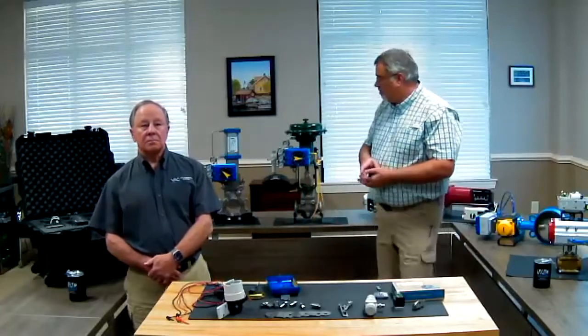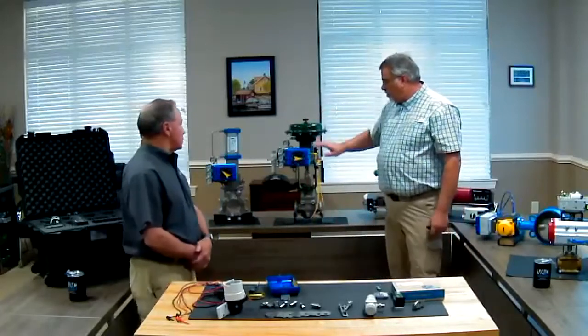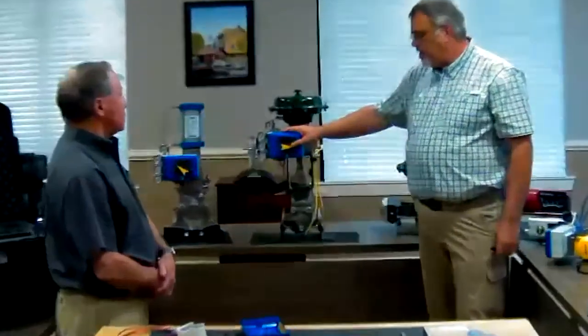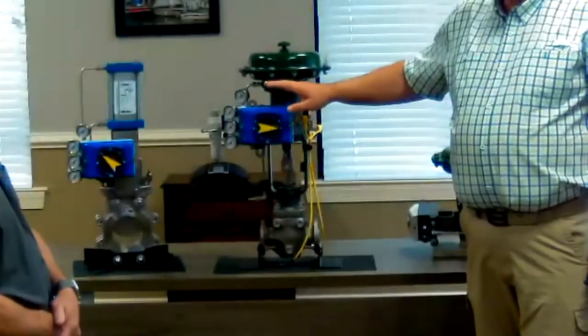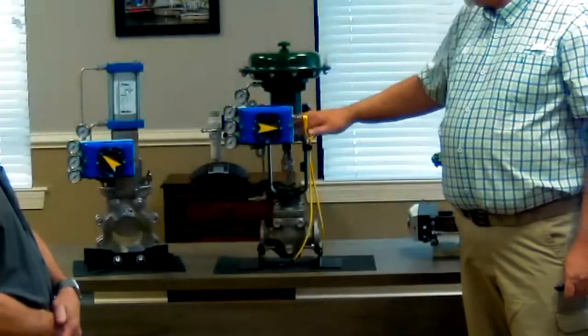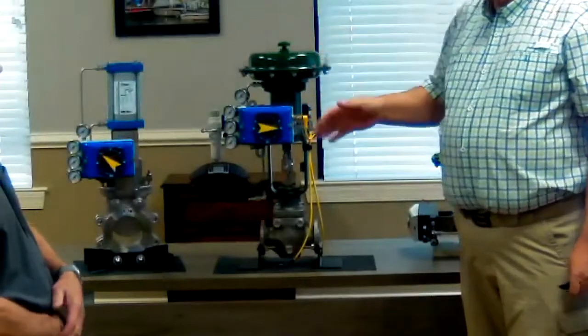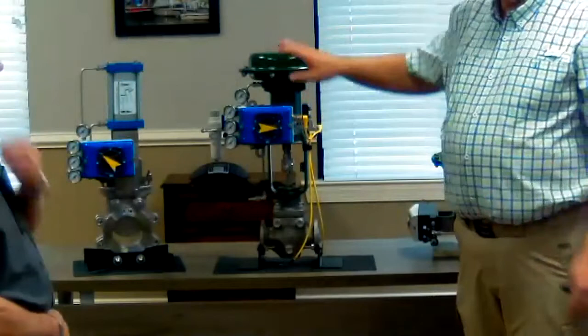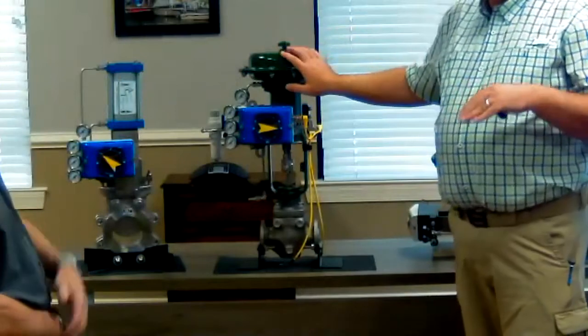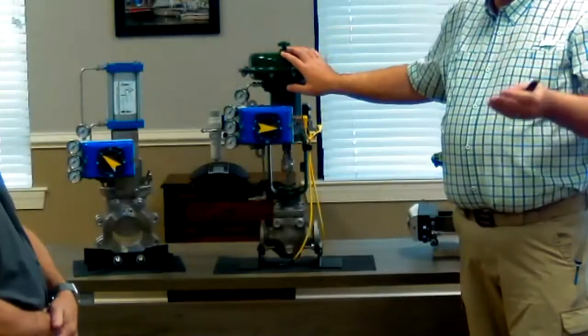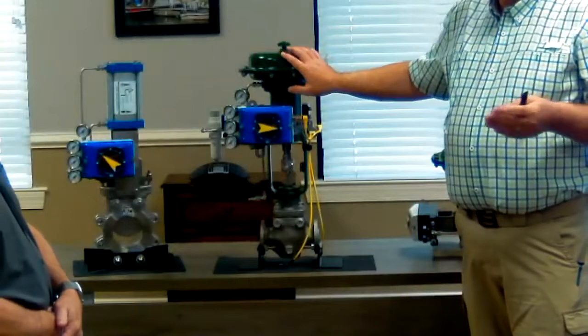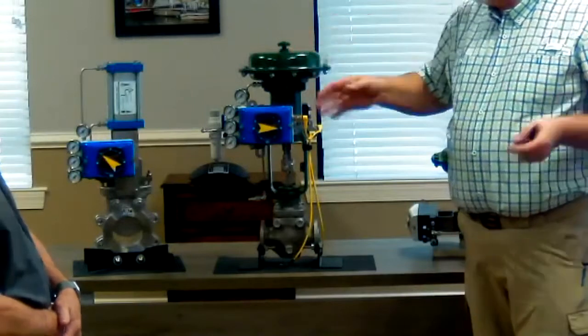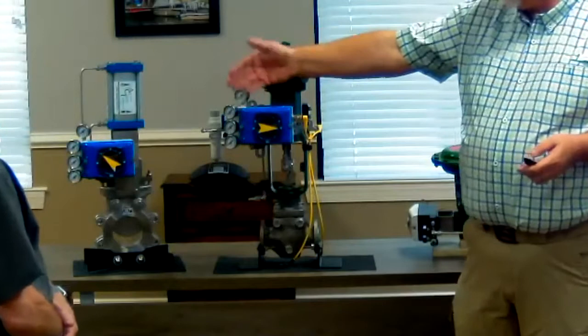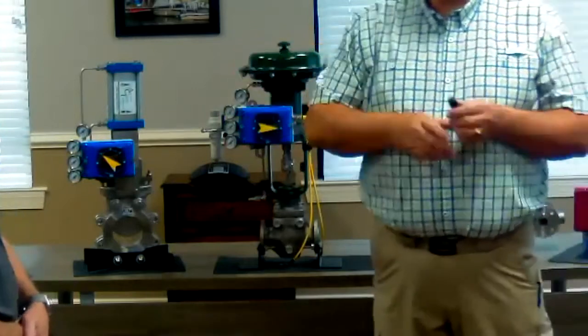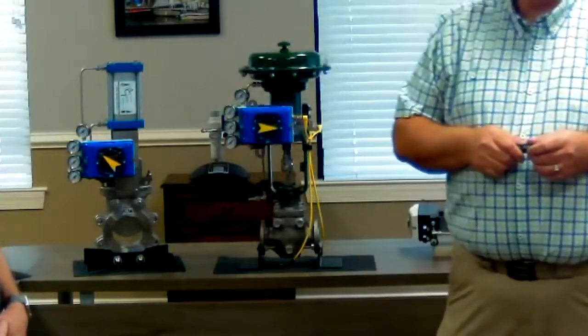We've got retrofit examples here. This is a Fisher E-body globe valve. We offer this kit in stainless or carbon steel, very easy to install. It fits a wide variety of these valves, strokes from a half inch to 2 inches with one kit. The kit that's on that Samson valve will fit not only Samson, but many other small globe valves with short strokes.